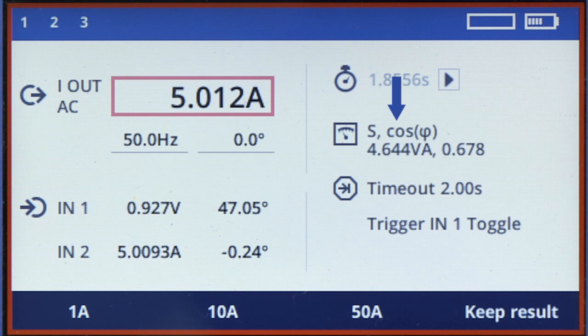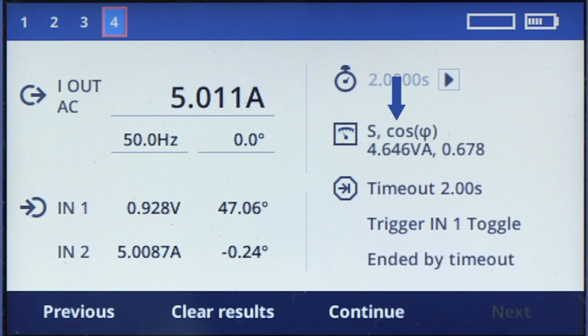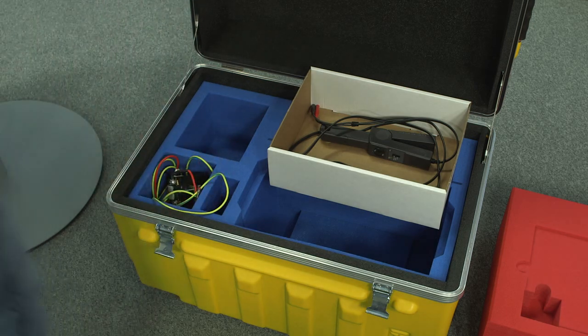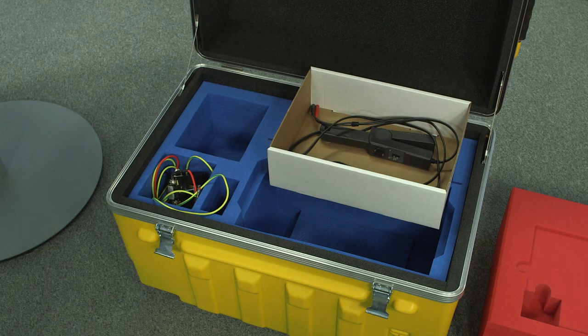The measurement shows the secondary burden of the CT. We're done. Please disconnect everything and put the CT, the current clamp, and the relay back into the case.